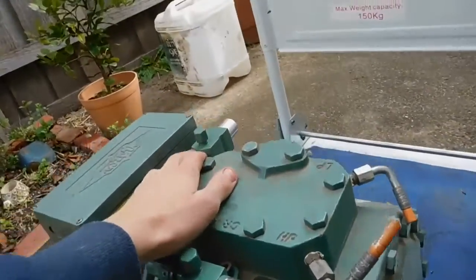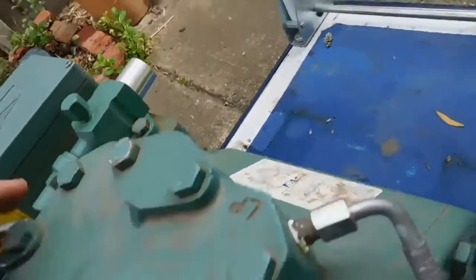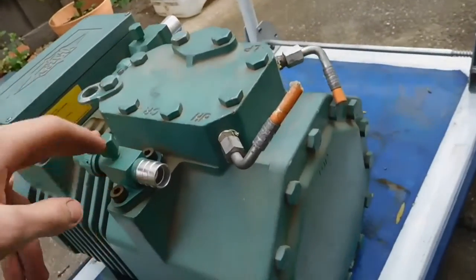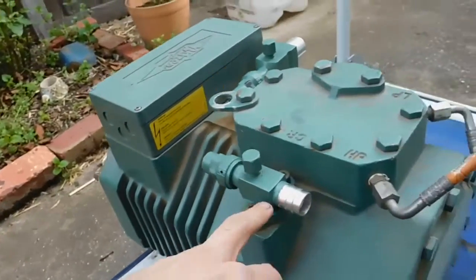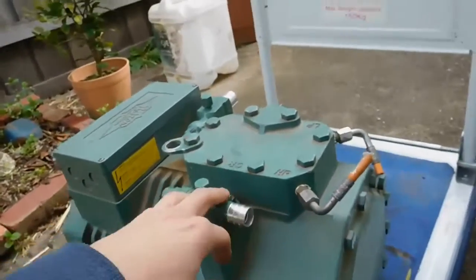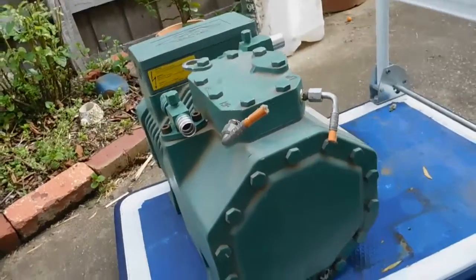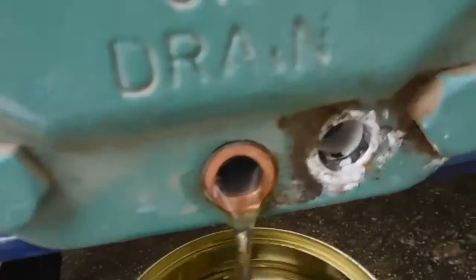You've got your suction valve here - on any compressor that'll always be the larger pipe. Suction comes in through a little strainer into the head, pistons compress it to high temperature, then it comes out discharged either through an oil separator if the system has one, or straight into the condenser. The oil is definitely an interesting color, so I have a feeling she may be shot inside.